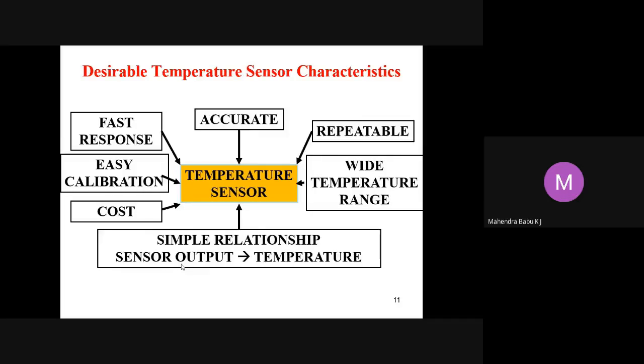Another important characteristic that the temperature sensor should have is repeatability. As you know, repeatability is defined as the deviation between measurements in a sequence where the object under test is the same and approaches its value from the same direction every time. Measurements have to be made in a short enough time duration so that it does not allow significant long-term drift. Repeatability is usually specified as a percentage of sensor range.